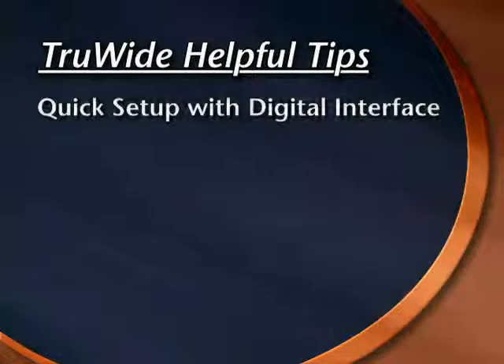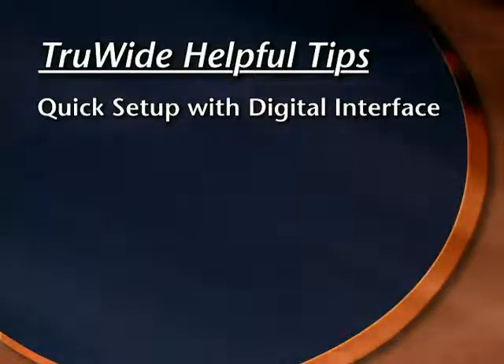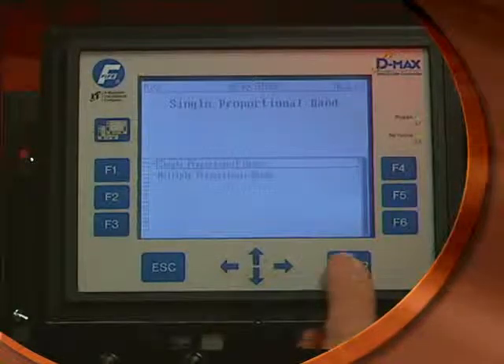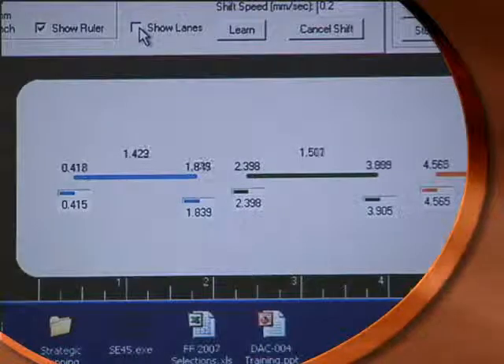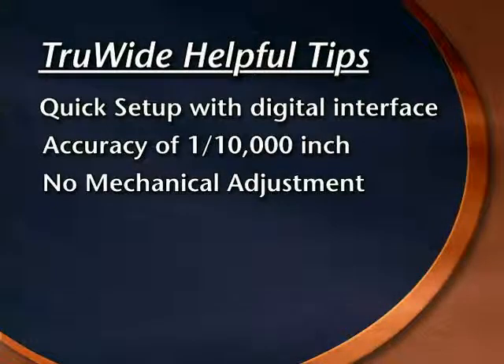Please note the following items when using the TruWide sensor. The entire setup process for moving the desired location of an edge can be performed in a matter of seconds. The 16-bit resolution of the TruWide sensor means that an edge can be sensed with an accuracy of one ten-thousandth of an inch. There is no mechanical adjustment necessary.